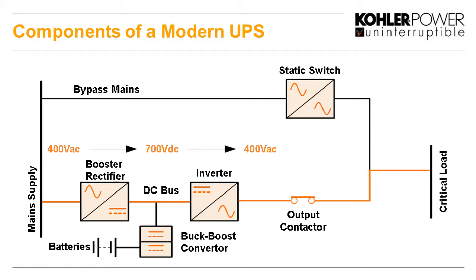So a static online double conversion UPS looks typically something like this. The line at the top, the bypass mains, feeding a static switch, or sometimes called just a bypass line or reserve line. Now that is in the event that the UPS needs to be maintained, or if there's a problem with it, or if there's an actual problem on the critical load itself, we can transfer no break onto the static switch to keep the critical load running. At the bottom there we see the batteries, and they can be connected onto the DC bus in various ways depending on the manufacturer. But what will happen is when the mains fails, the booster stops working and the batteries connect to the DC bus, supplying the inverter with power to continue with the critical load.